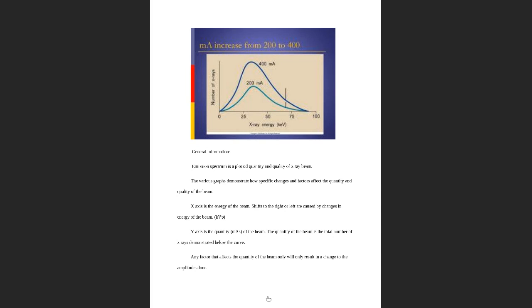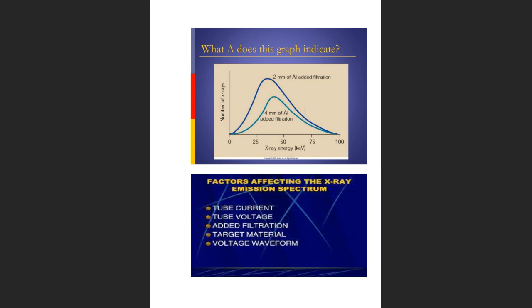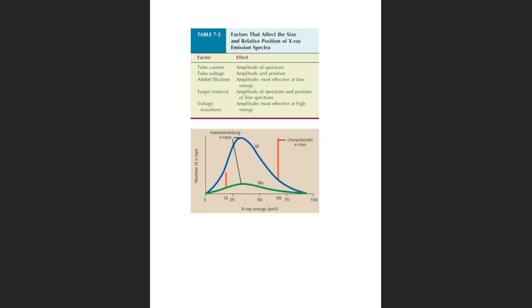But one of the things that we recognize is, I'm trying to get to target material one so I can show you what I'm talking about. There we go. So this is a molybdenum target. For all of you that are aware already, a molybdenum target is used in mammography. Mammography uses very low kVp and higher mAs values.